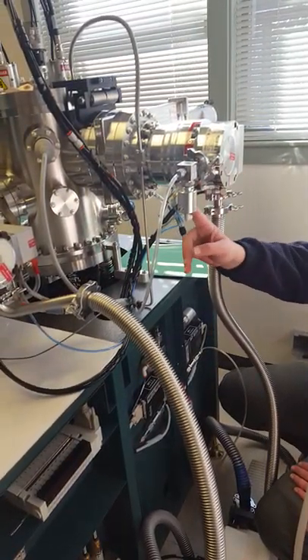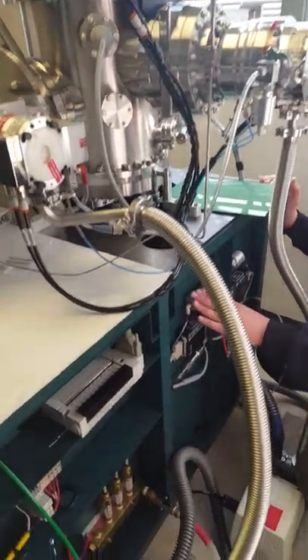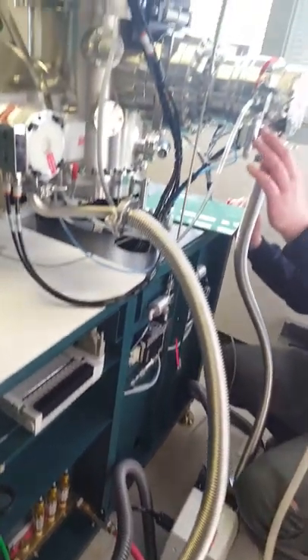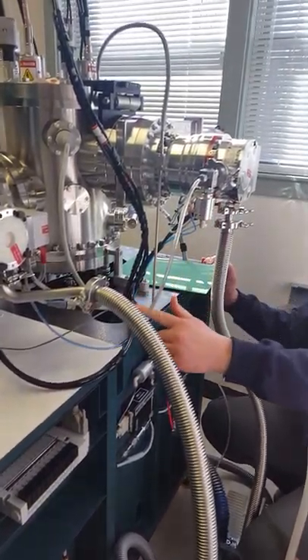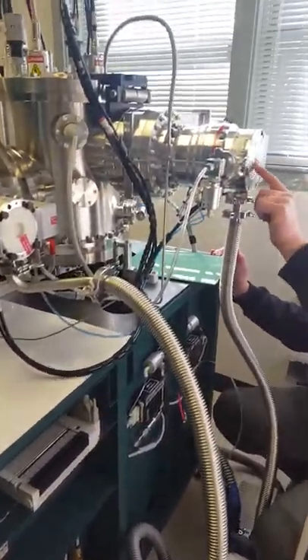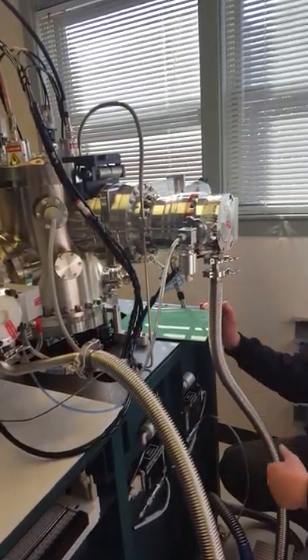This right here is a purge valve, used for oxygen processing. It will open when you open this isolation valve to deliver oxygen into the system. At the same time, it automatically opens this valve, which allows venting nitrogen to get into the back of the turbo to protect the bearing from the oxygen going in.